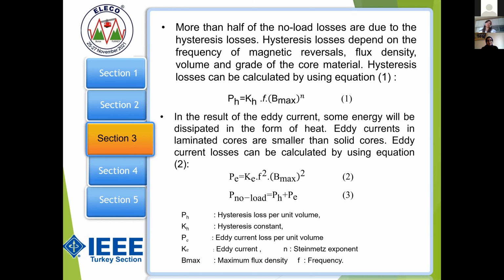These are some of the formulas to find the hysteresis losses and eddy current losses. As I told, the major part of the no load losses is due to hysteresis and eddy current losses. We can also see that about half of the no load losses are due to hysteresis losses, and this depends on the frequency of magnetic reversals, flux density, volume, and grade of the core materials. So we can find the hysteresis losses with equation 1. Similarly, eddy current also depends on the lamination of the transformer. The smaller the lamination, the lower the eddy current losses will be. So we can decrease the eddy current losses by decreasing the thickness of the lamination. The smaller the size, the fewer the losses, as I told. Solid cores will have more eddy current losses. Equation 2 or 3 can be used to find the eddy current losses and overall no load losses.